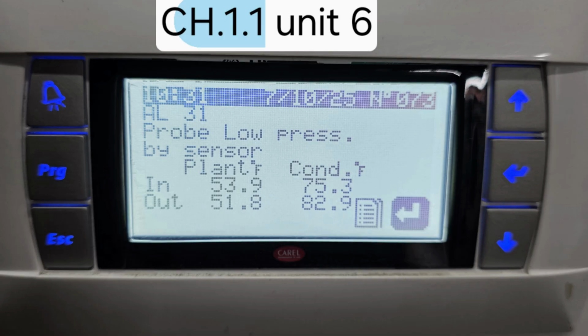In the picture, you can see that we have low pressure alarm on the heat pump. High flow and low delta T on the evaporator loop, meaning possible low pressure alarm. The evaporator, water to refrigerant heat exchanger, transfers heat from the water loop into the refrigerant. When flow is too high, the water passes through the evaporator too quickly. The temperature difference, delta T, between water entering and leaving becomes too small. The refrigerant absorbs less heat per pass. As a result, the refrigerant may not vaporize fully before reaching the compressor suction, causing low suction pressure, low side pressure. The controller will detect this as a low pressure alarm or low evaporating temperature alarm. In short, high water velocity in evaporator, reduced heat absorption, low suction pressure, low pressure alarm.